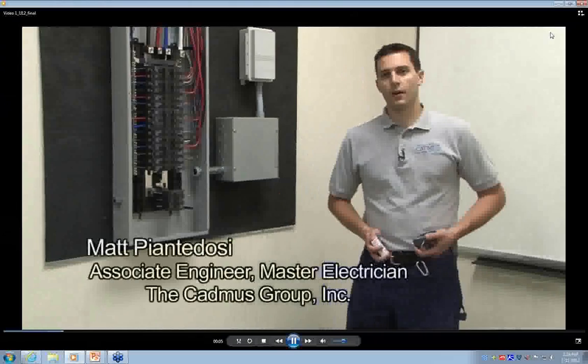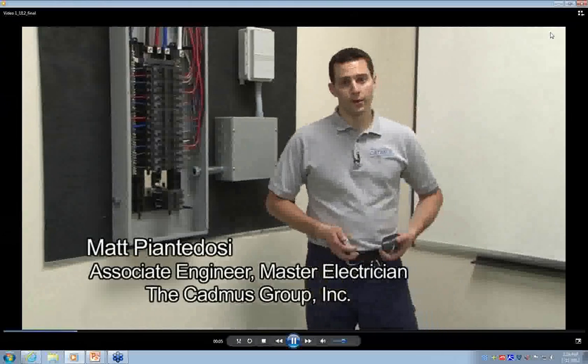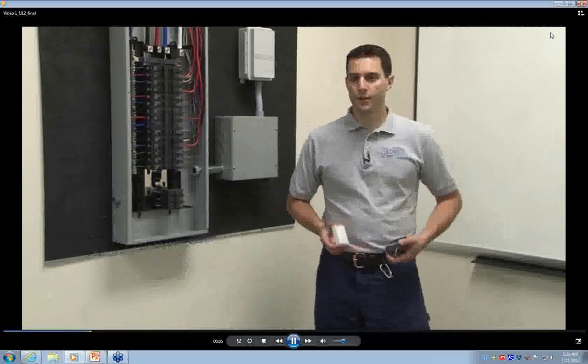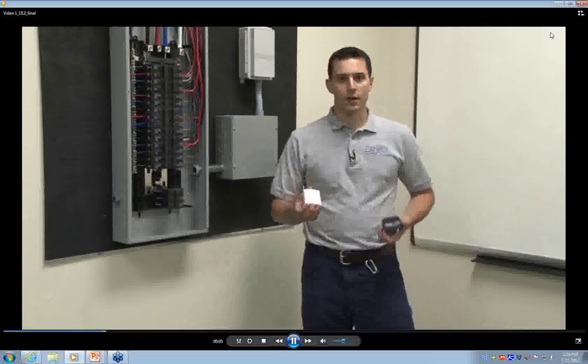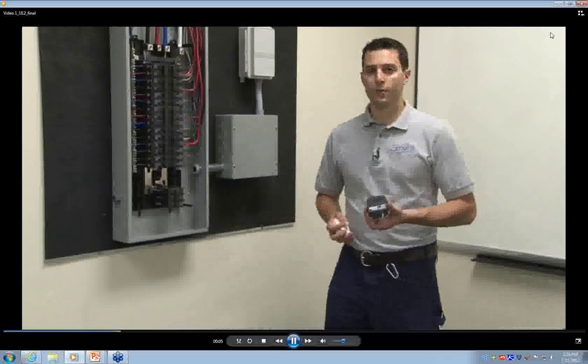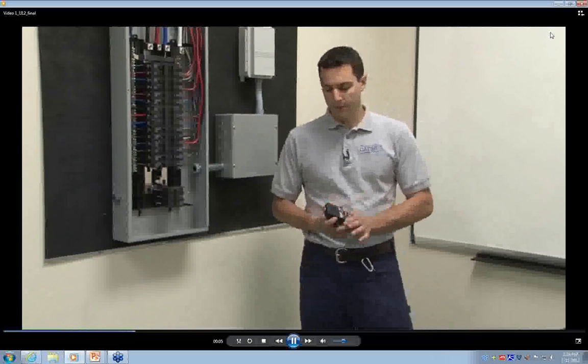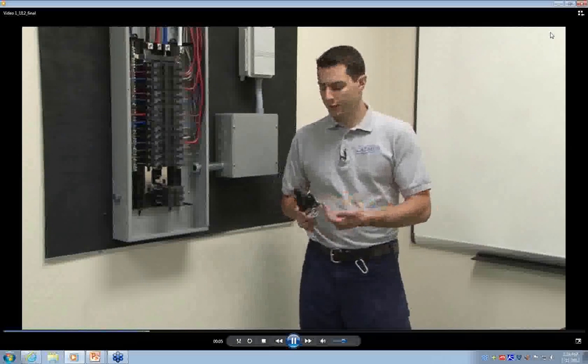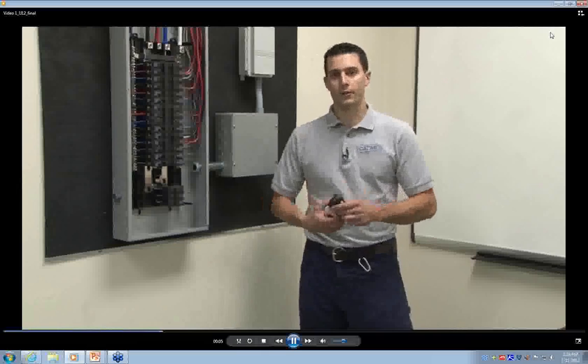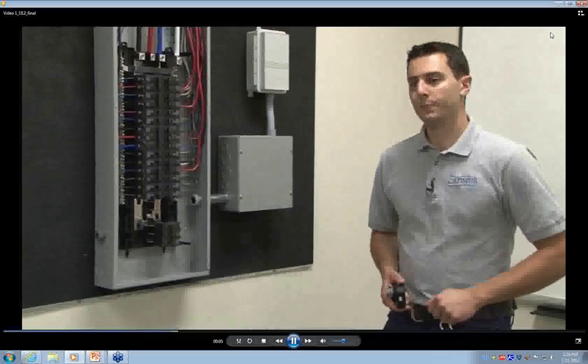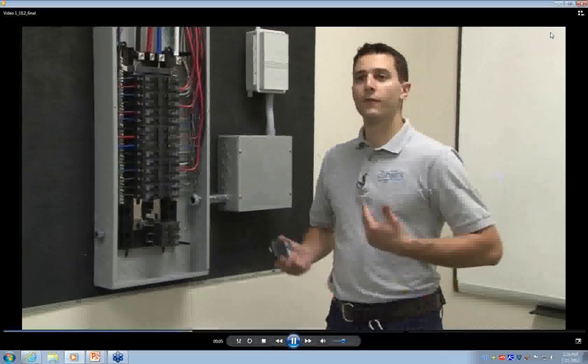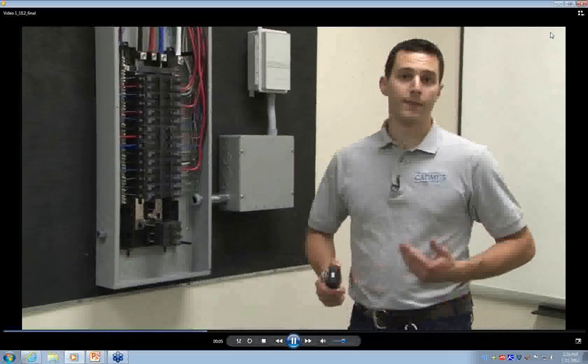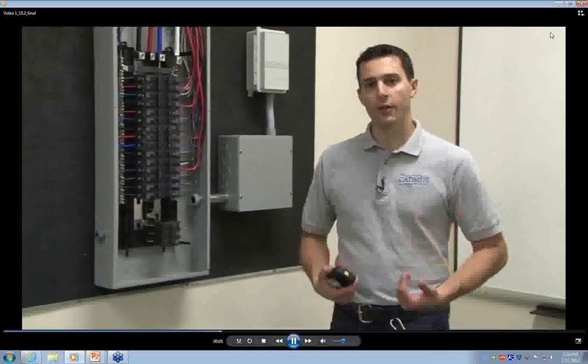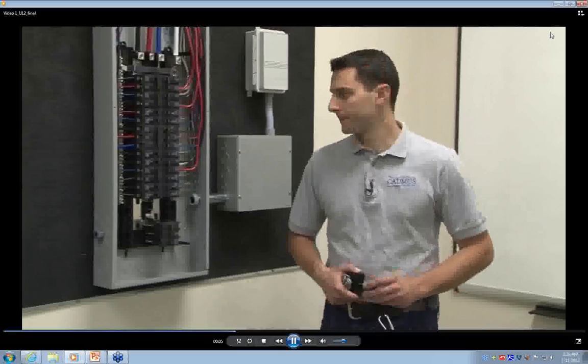We'll now install a data logger on a single circuit to monitor the amperage. We'll do so by using an Onset HOBO U12 data logger and a CTV-A, which is a split-core current transformer. This particular current transformer is not directional, so it doesn't matter which end the wire goes in. We'll be working with our demonstration panel board, which is de-energized, so we can focus on the meter installation. If this were an energized panel board, I'd be wearing all the necessary safety gear to work in it.